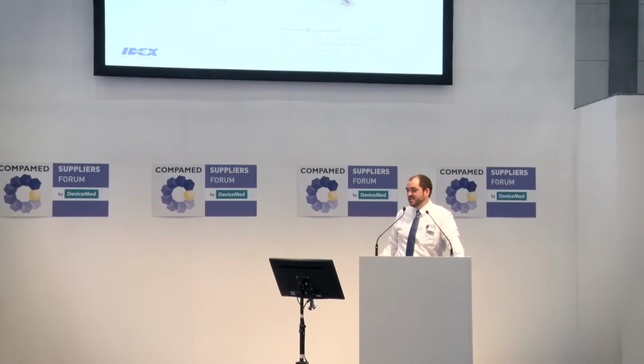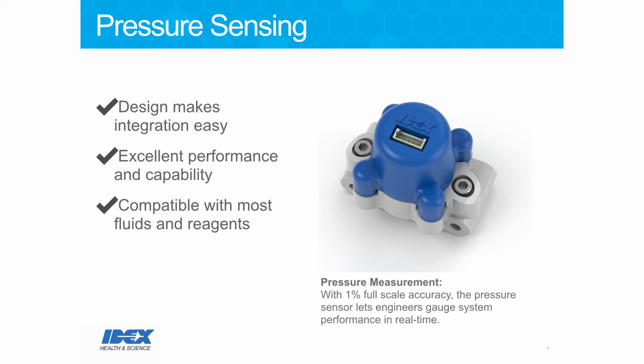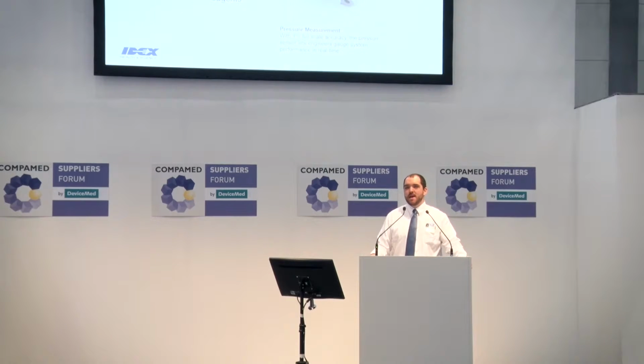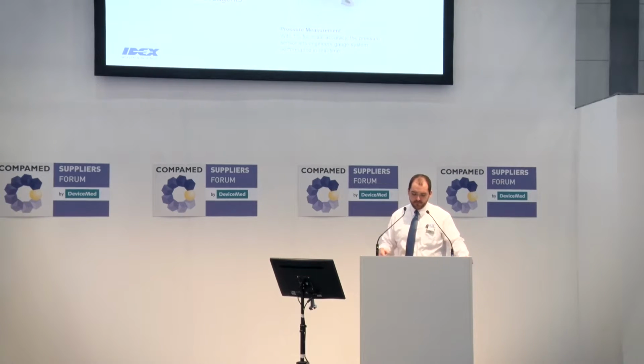The first one we have here is the pressure sensor. We have two options for this. We're going around saying they're a modular pressure sensor. What we mean by that is there are two options. There's an option to use quarter 28 fittings. So that's just a standard fitting and tubing system to attach to it. We're also offering a manifold mount option. Now the manifold mount option would mount to a flat surface. You could bolt it right on. It's just two screws. It's 3 inch-pounds to attach it to a manifold. So that means no special design. It's just simple fluidic paths and allows you to get your prototypes up and running really quickly without having to have a special interface for them.